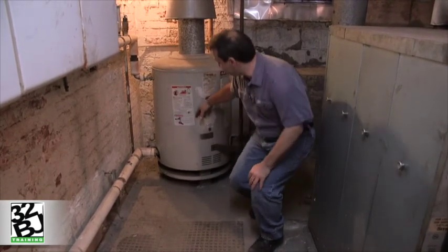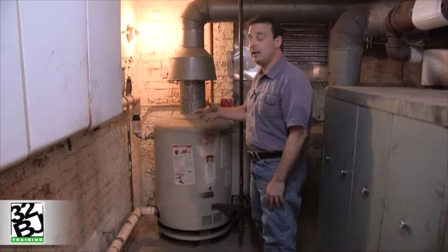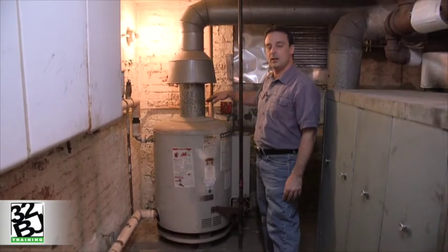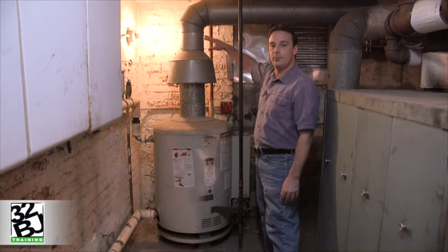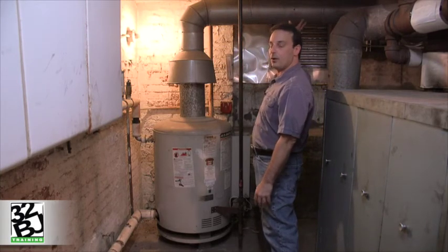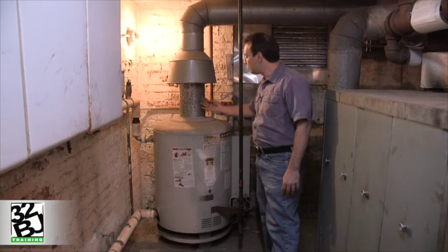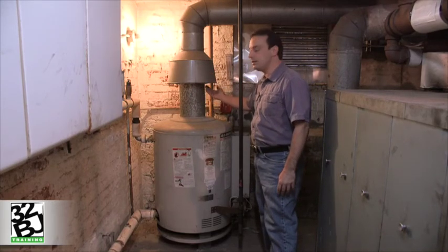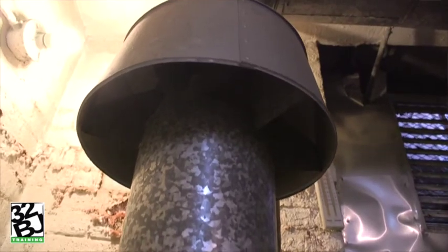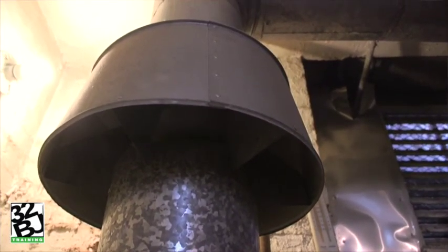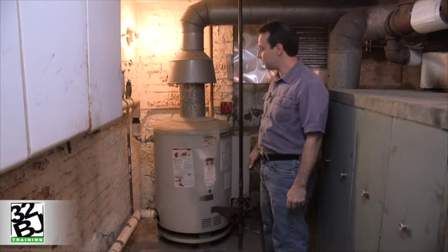Those gases travel up through the hot water heater, giving off their heat to the hot water, and eventually exiting the hot water heater through the breeching on top to carry it over to the chimney. This bell damper allows for dilution air to enter into the breeching in an attempt to maintain proper draft, so the gases of combustion will rise up through the chimney.